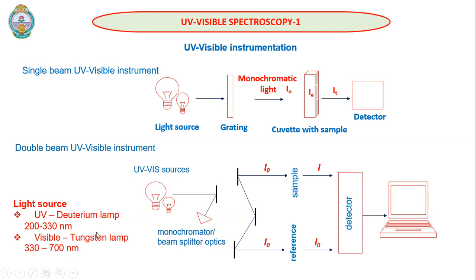We will have two light sources for the UV visible spectroscopic technique: the deuterium lamp for the UV source, and the tungsten lamp for the visible light source. When we pass light onto the sample solution, the sample absorbs light. The process of absorption and the calculations were derived by Beer-Lambert's law. August Beer and Johann Heinrich Lambert were individually working on the absorption of light.